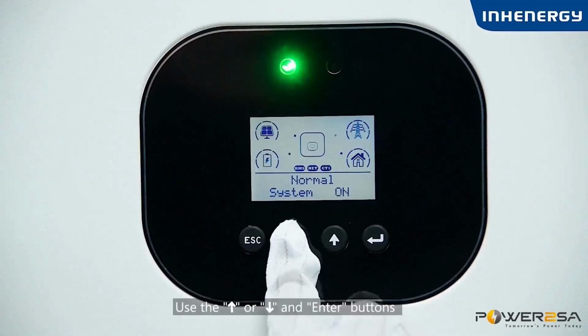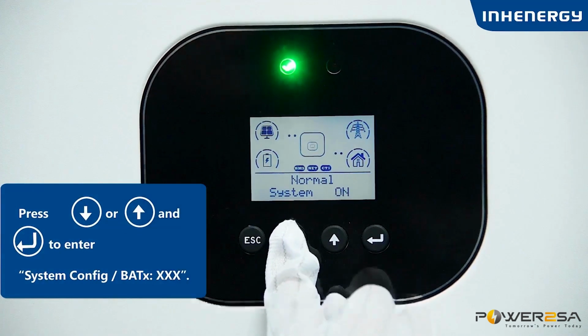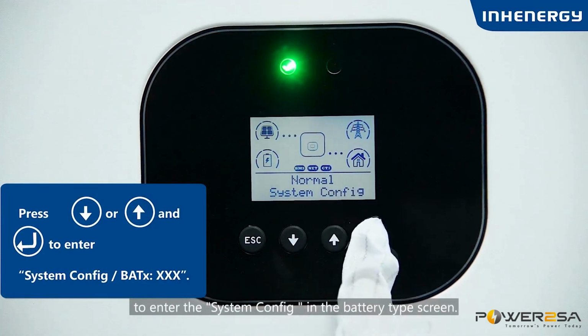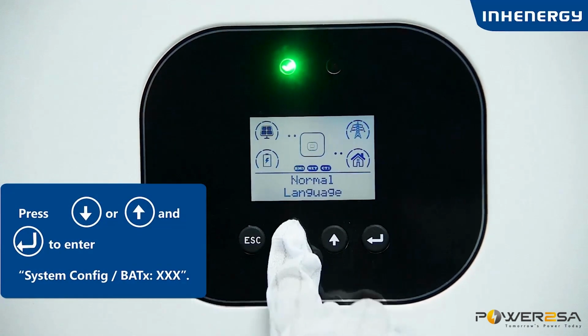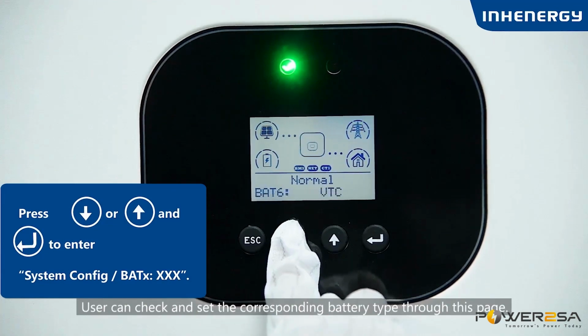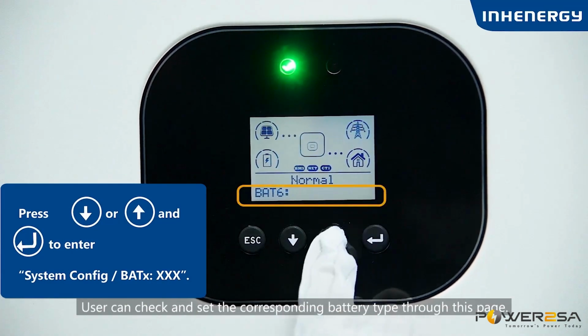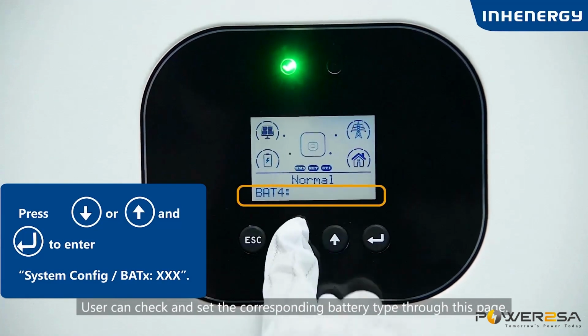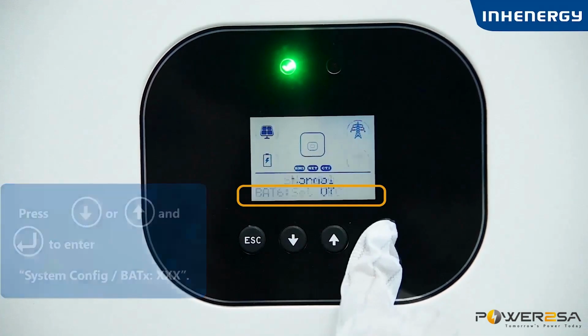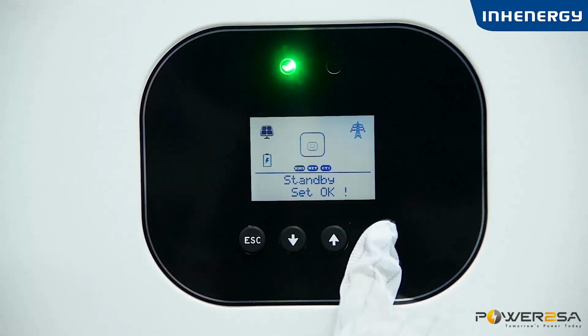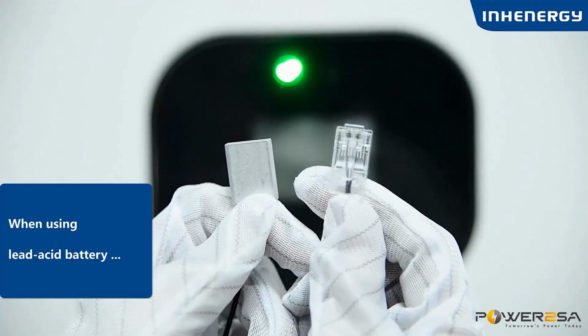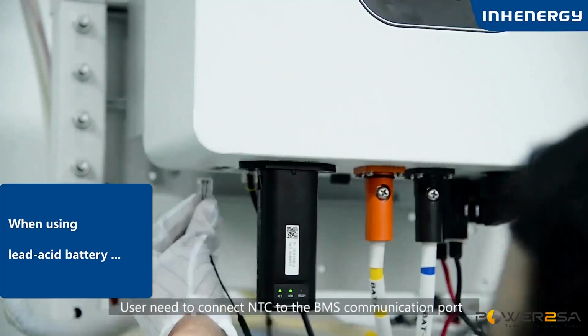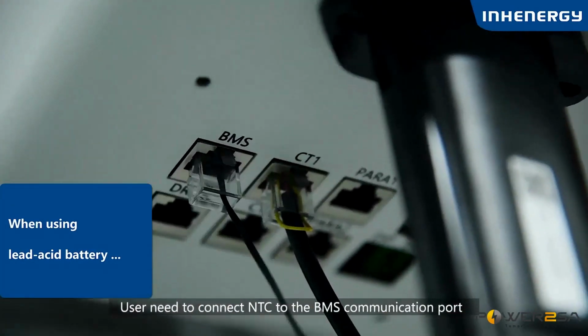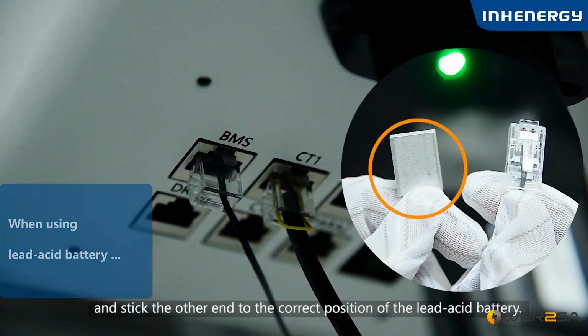Use the up or down and enter buttons to enter the system config in the battery type screen. User can check and set the corresponding battery type through this page. When using lead-acid battery, user needs to connect NTC to the BMS communication port and stick the other end to the correct position of the lead-acid battery.